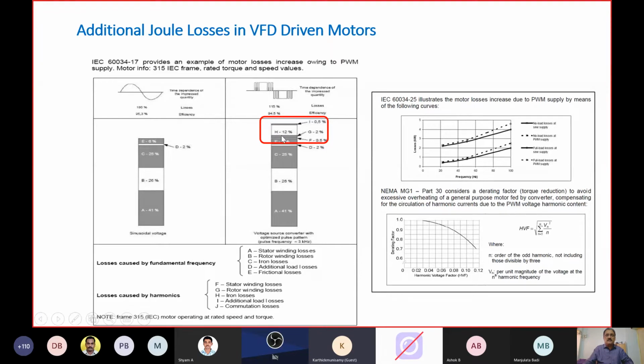These additional losses are called losses in the iron or additional joule losses. So independently, looking at the motor alone, the efficiency may come down. I don't know if you are aware, when the original IEC 60034-30 was announced, they had given that IE2 motors with a VFD will exhibit the characteristic efficiency of IE1. IE3 motors with a VFD will exhibit IE2 efficiencies. This was originally discussed. Today, of course, IEC has come with a separate standard for testing both motor and VFD put together.